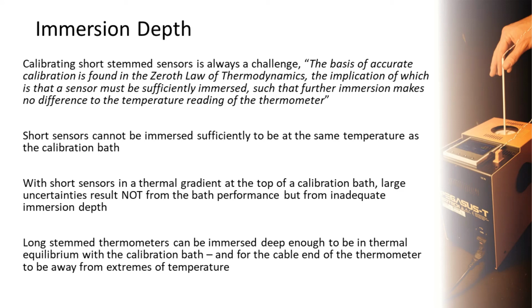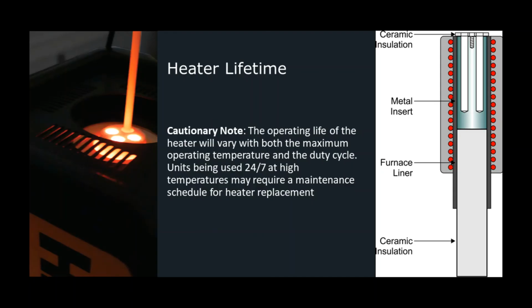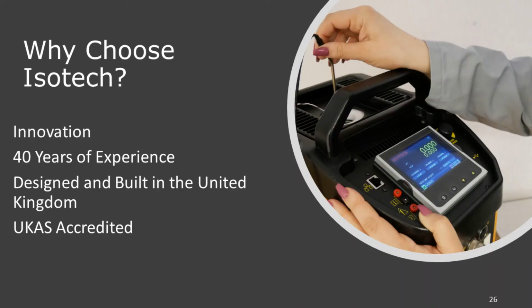Long-stem thermometers can be immersed deep enough to be in thermal equilibrium with the bath, and for the cable end of the thermometer to be away from any extremes of temperature. The operating life of the heater will vary with both the maximum operating temperature and the duty cycle. Units being used constantly at high temperatures may require a maintenance schedule for heater replacement.